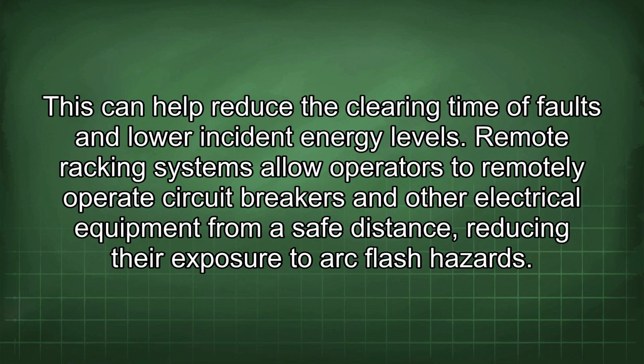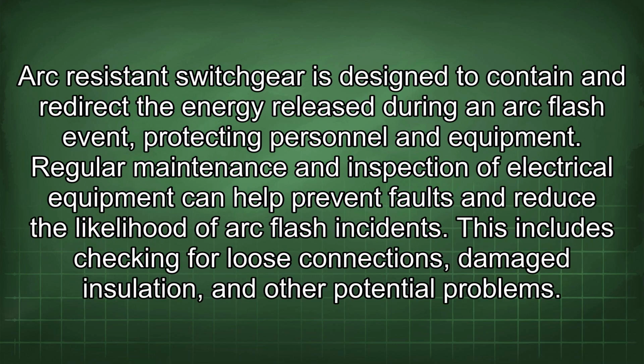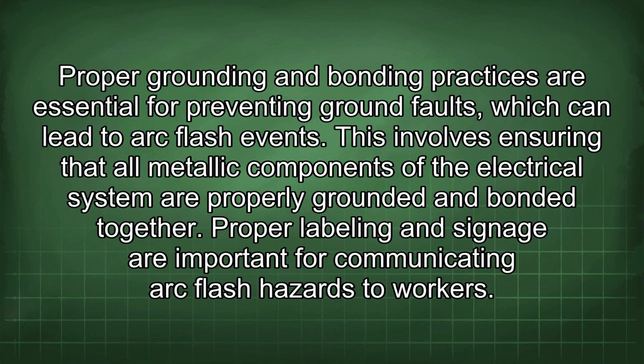Remote racking systems allow operators to remotely operate circuit breakers and other electrical equipment from a safe distance, reducing their exposure to arc flash hazards. Arc-resistant switchgear is designed to contain and redirect the energy released during an arc flash event, protecting personnel and equipment. Regular maintenance and inspection of electrical equipment can help prevent faults and reduce the likelihood of arc flash incidents. This includes checking for loose connections, damaged insulation, and other potential problems. Proper grounding and bonding practices are essential for preventing ground faults, which can lead to arc flash events. This involves ensuring that all metallic components of the electrical system are properly grounded and bonded together.